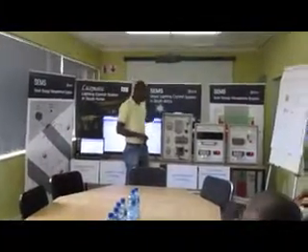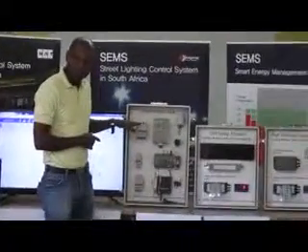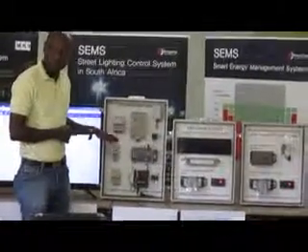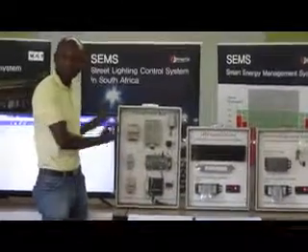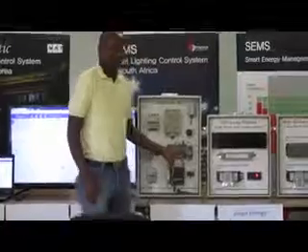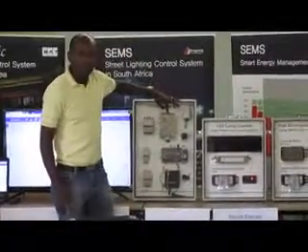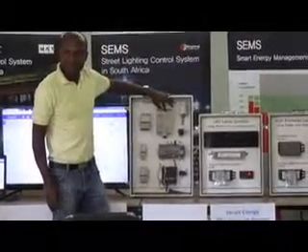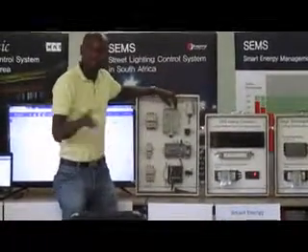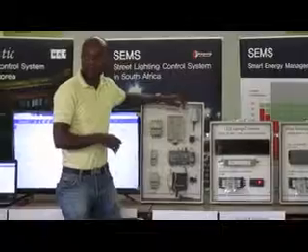This box, we call it the concentrator box, because it has our concentrator. On our left hand side, we have what we call the breakers, the second breaker. This is the electrical component we put on the left hand side. On our right hand side is the communication component. On top here is a surge arrestor. It allows us to protect the device against lightning.